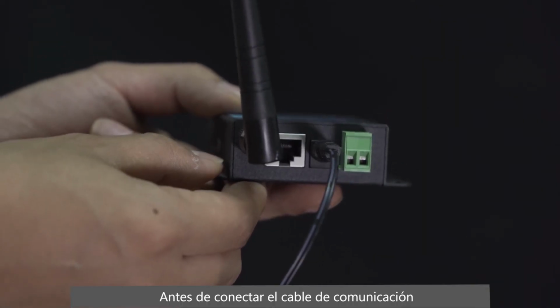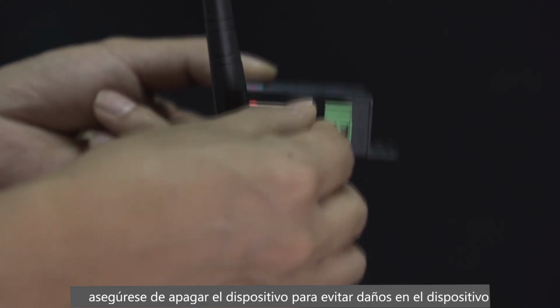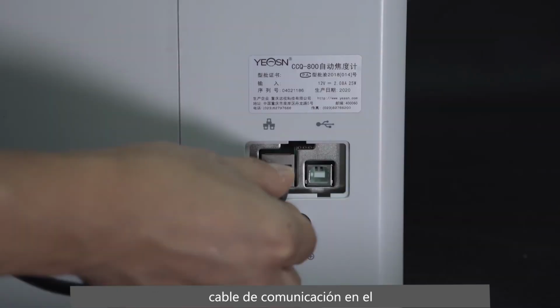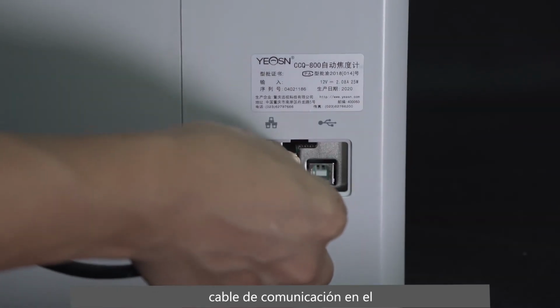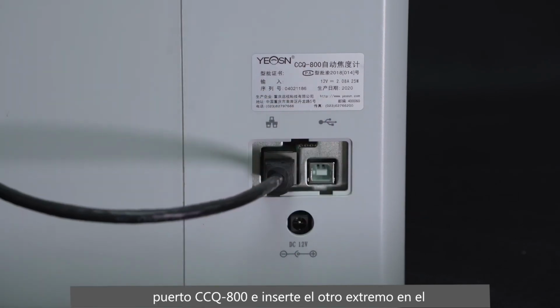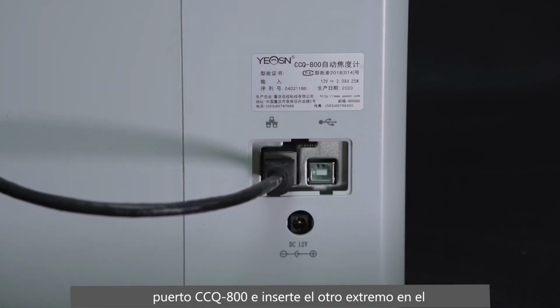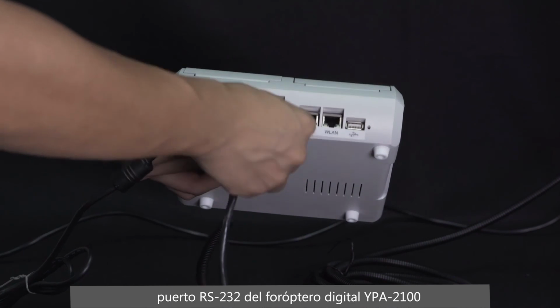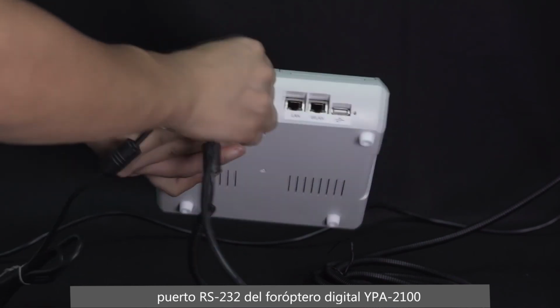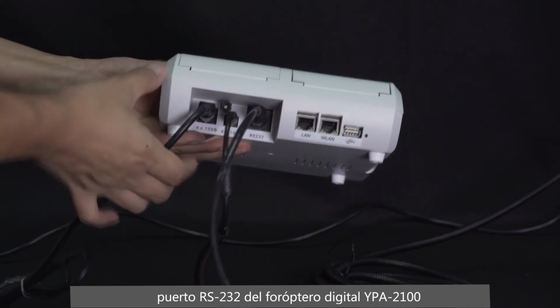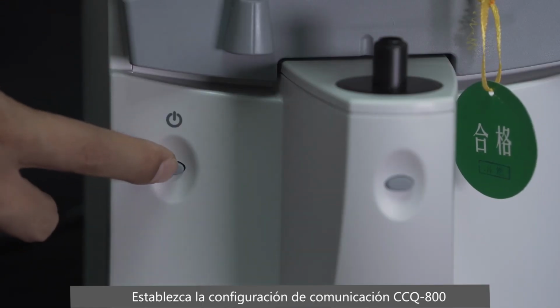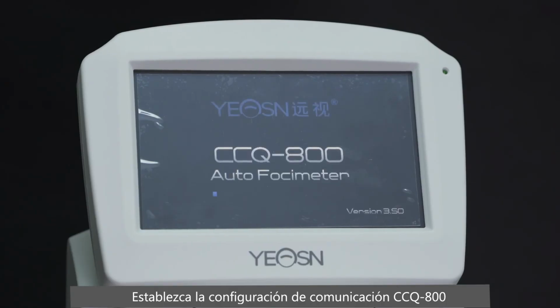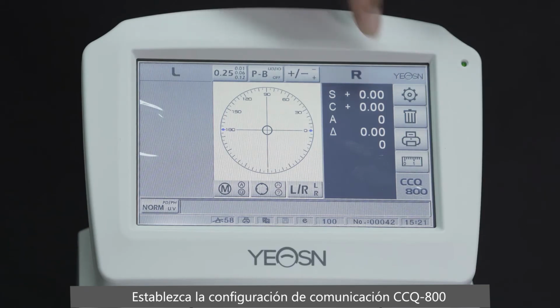Wired connection for CCQ800 auto lens meter. Before connecting the communication cable, be sure to turn off the power of the device to avoid damage to the device. Insert one end of the crystal head of the communication cable into the CCQ800 port, and insert the other end into the RS-232 port of the digital phoropter YPA2100. Boot up. Set up CCQ800 communication configuration.